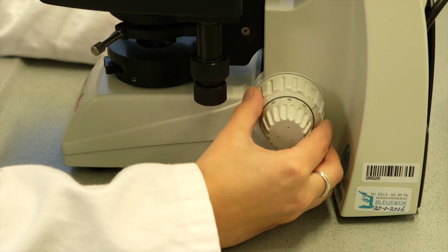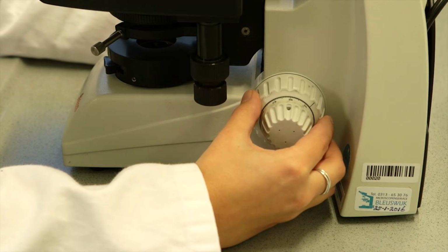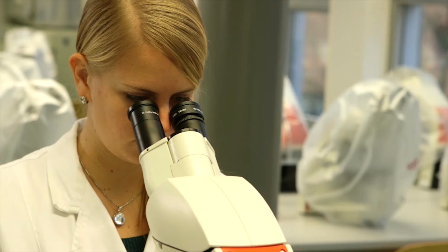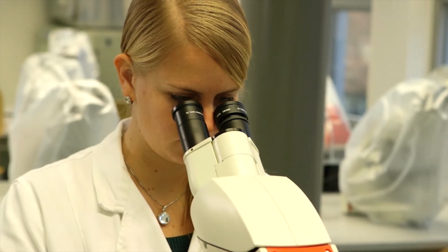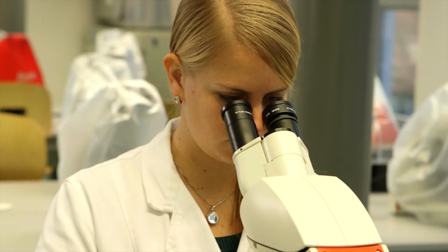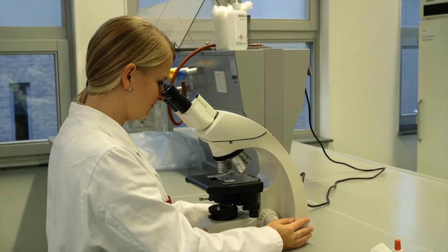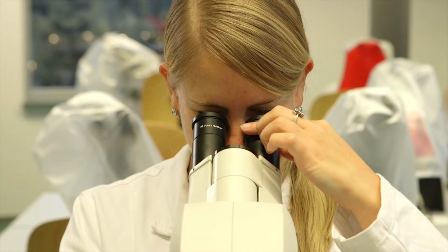Start by turning the table to the highest position by turning the coarse focus knob. This can only be done with the 10 times objective in place. Always keep your eyes on the slide to make sure that the slide and objective do not collide.